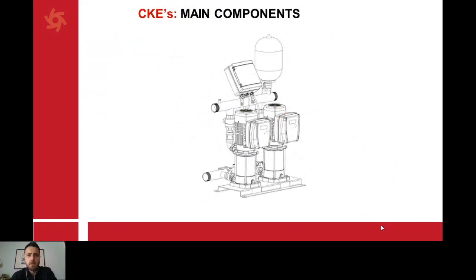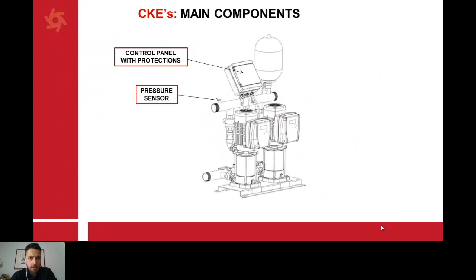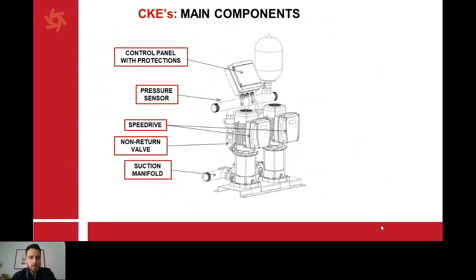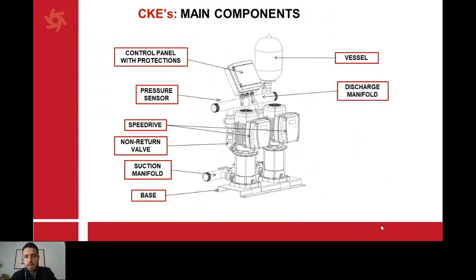Which are the main components of a booster set? Talk about the control panels, because it has everything needed for the installation. The pressure sensor, SPEEDRIVE, non-return valve, this is a very important issue, suction manifold, the base plate, the vessel, discharge manifold, and the pumps.